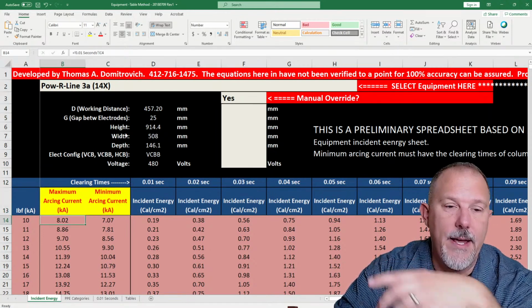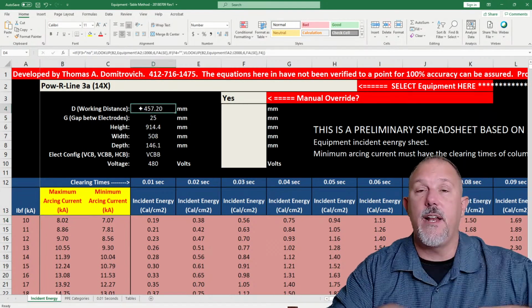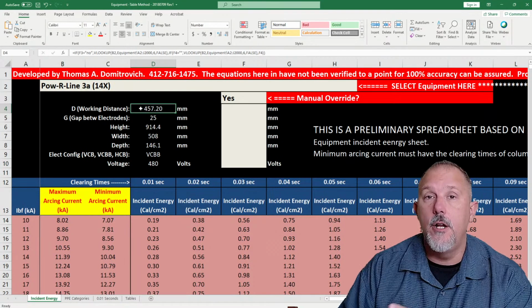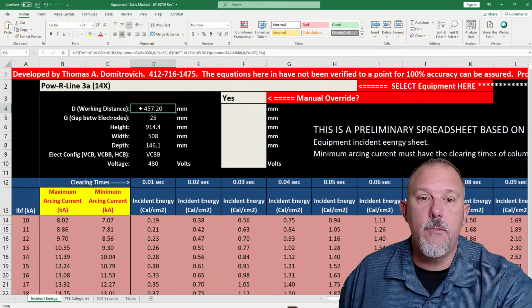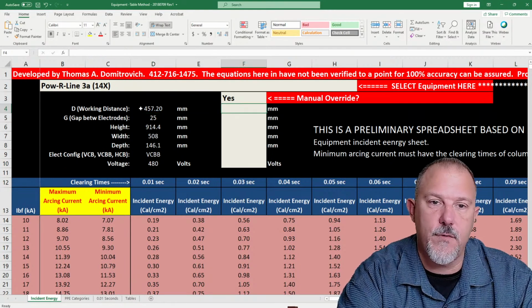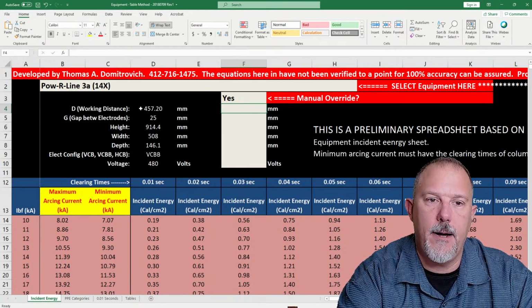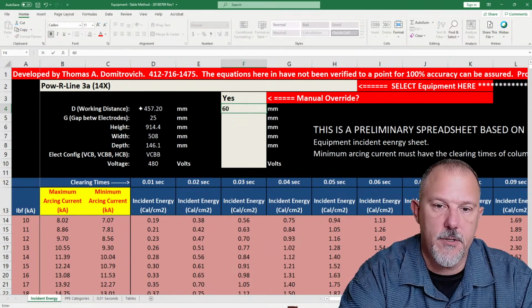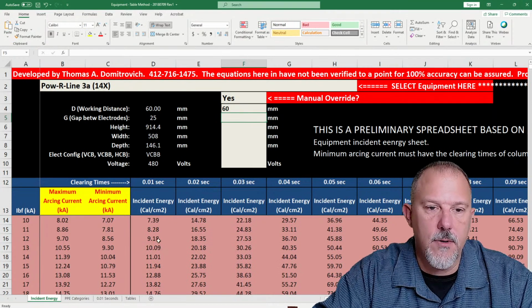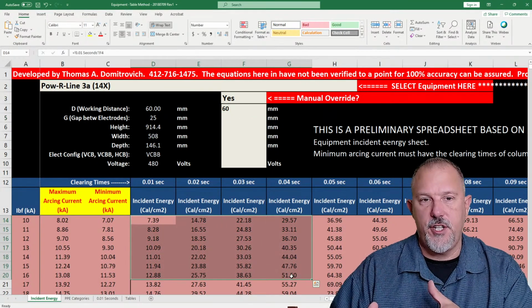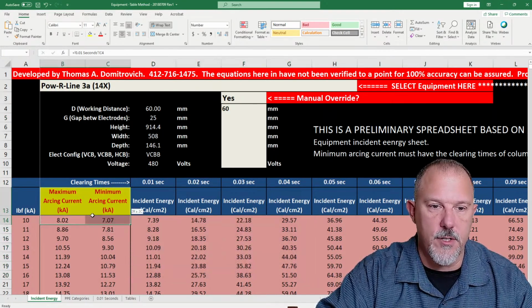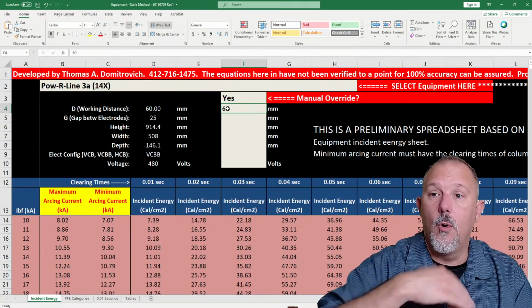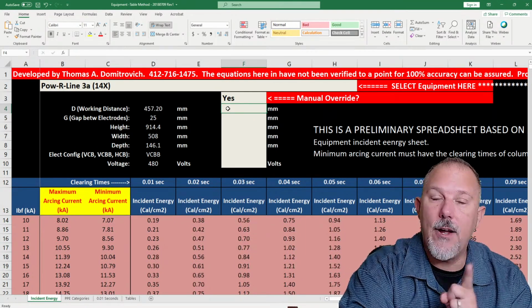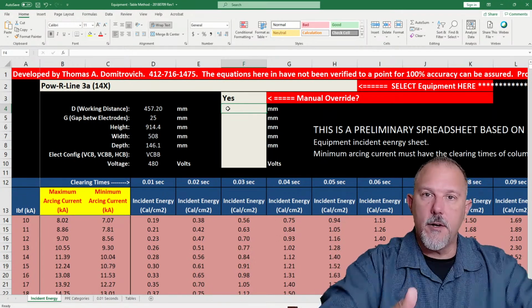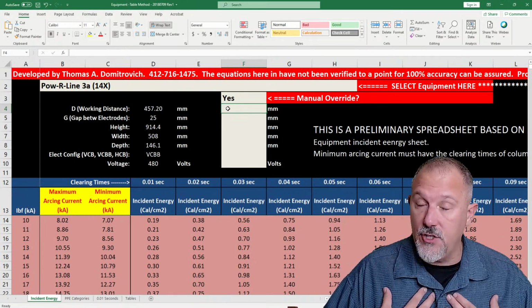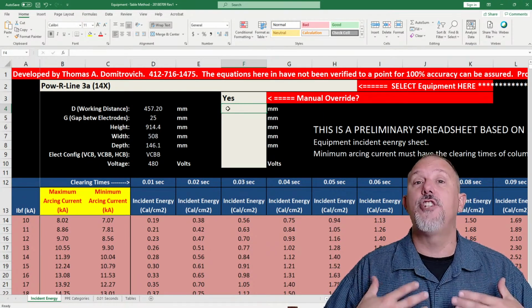I have the key parameters that IEEE 1584 uses to calculate incident energy. I have to know my working distance. If I change my working distance from 457 millimeters to 60 millimeters, my energy values change, all of those are energy values, not arcing currents. These are arcing currents. What you'll notice is I changed the working distance, but my arcing currents don't change, because the arcing current is not driven by how close I am to the equipment. What is driven by how close I am? How much energy I'm going to experience.